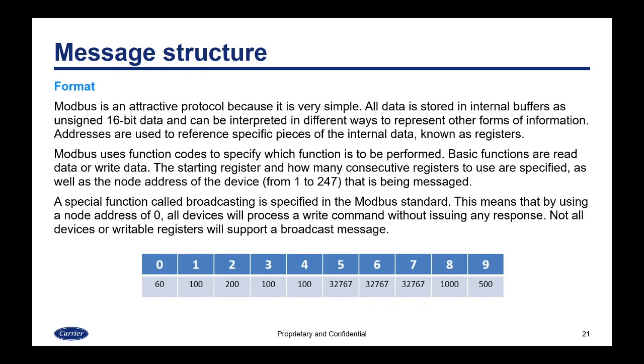Modbus is an attractive protocol because it is very simple. All data is stored in internal buffers as unsigned 16-bit data and can be interpreted in many different ways to represent other forms of information. Addresses are used to reference specific pieces of internal data known as registers.